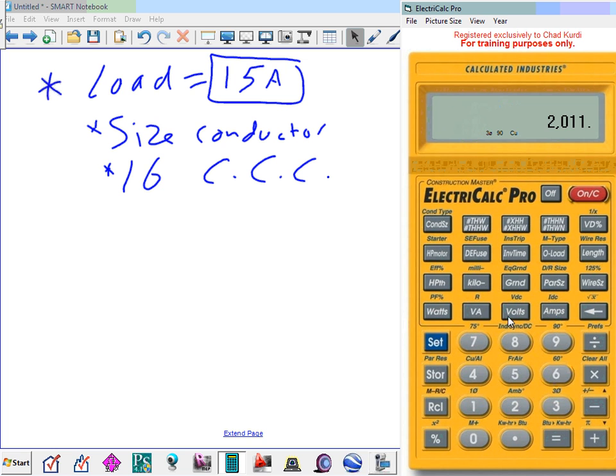Now let's tell my calculator what's the load that I need. I need 15 amps. Here's my 15 and hit the amps. Does it matter what the voltage is? Irrelevant of the voltage. 15 amps. Cool? Everybody's okay with that? So set to 90, so my insulation is THHN 90. We're sitting at 15 amps.